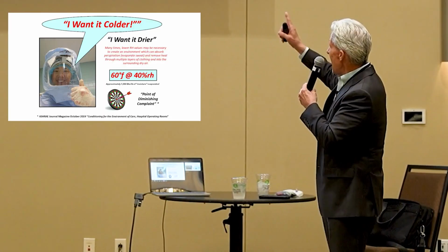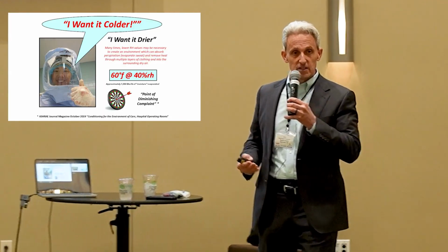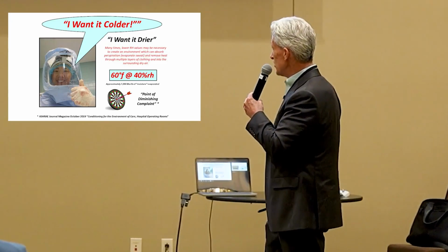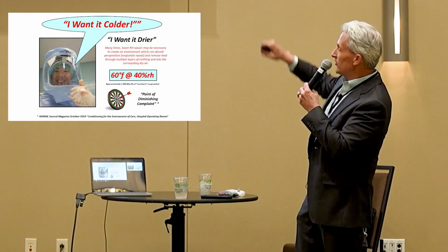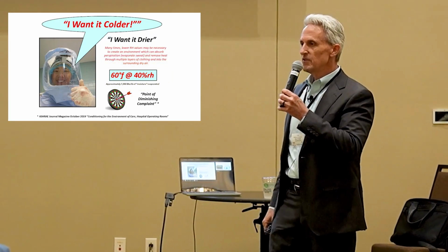Now, I suggest, and I have suggested for the last 20 or 30 years, and I've documented this in an ASHRAE Journal magazine article that I wrote in 2019, that what I call the point of diminishing complaint falls at the intersection of 60 degrees Fahrenheit and 40% relative humidity.